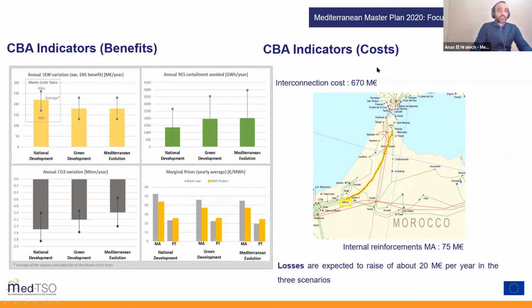For the results of network analysis, since it is VSC technology with a submarine cable, the interconnection cost will be more or less high, 670 million euros. We will also need to add two 400 kV lines in Morocco linking Sehul substation to Tetuan, reaching 75 million euros of capex. Losses are expected to rise, about 20 million euros per year in the three scenarios, since we are forcing flows through the HVDC.